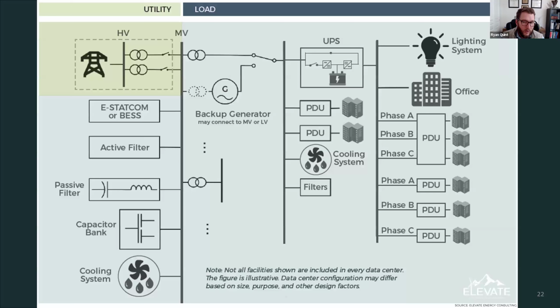We need to really think through what level of detail, what capabilities do we have to represent these devices on the grid. If it's a 50 megawatt load and it's a one-off, we maybe don't need such detailed models. But when we have large loads all over the system, interconnected right near large inverter-based resources, and these large loads are on the order of hundreds or thousands of megawatts, we really care about the technical details because they have such a significant impact on grid reliability.